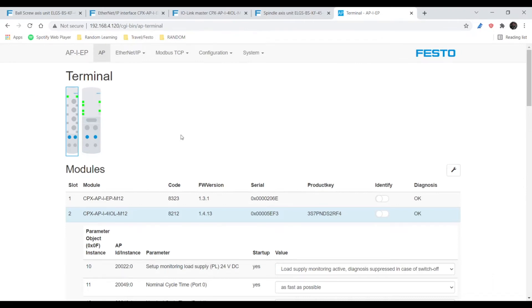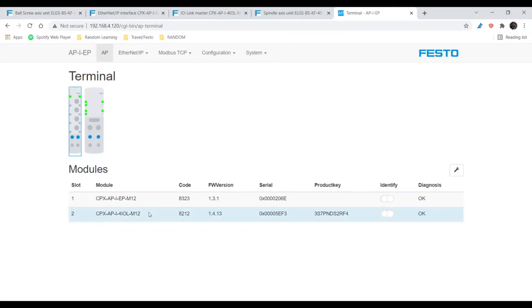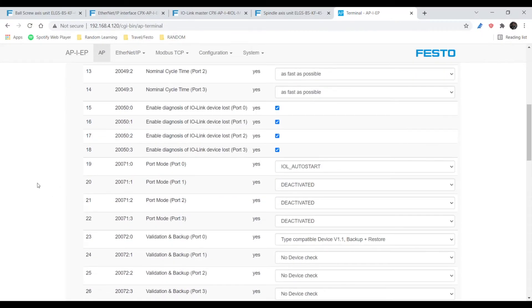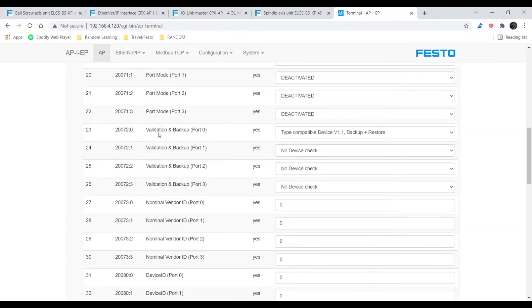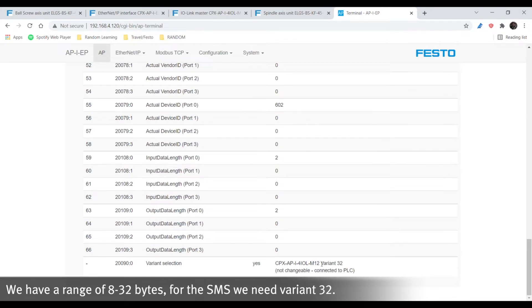From there we should have something that looks relatively like this. From here we're going to open up the IO-Link master module and check a few things. The first thing we're going to check is port 0, because I have my SMS connected to port 0. We're going to change that to IOL auto start. Then we're going to scroll down a little bit further, go to validation backup, and select device v1.1 backup and restore. Then we're going to go down and make sure that we have a variant that does not have an OE at the end.